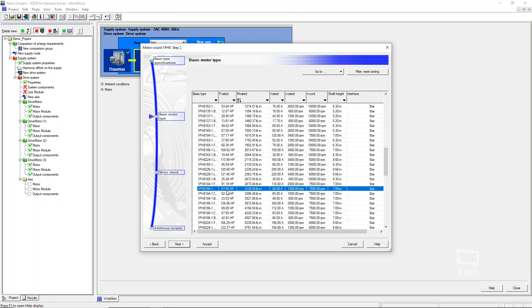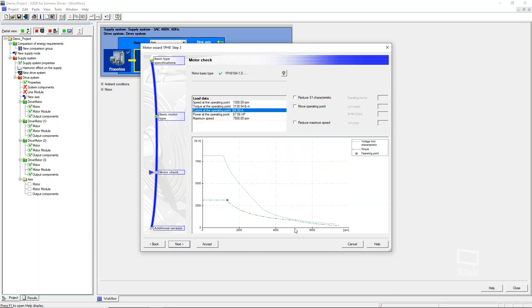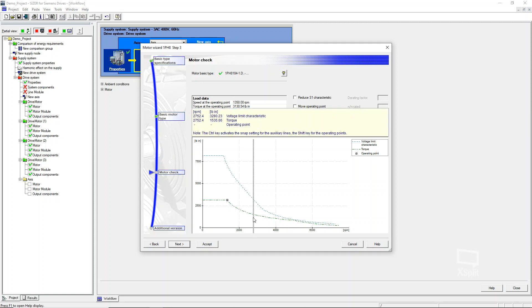We have this motor here that has that 3130. Now, if we notice something here, the horsepower ratings on these are quite different. And that is because that horsepower is based off of the torque at the rated speed. So kind of going in and thinking, this may not be the type of motor that we're wanting because it's a lower RPM motor. And I'll show you why we click next. It's going to show us this torque curve, which kind of looks the same as what we had before. But if we go out here to that 2600 RPM again, then we actually have less torque available to us out there because that torque is dropping off a lot quicker.